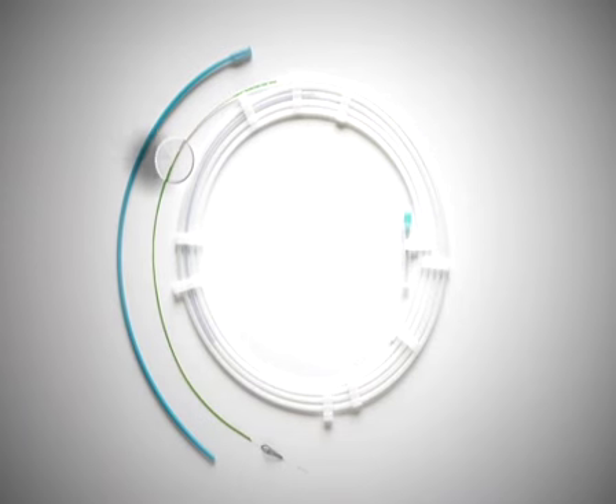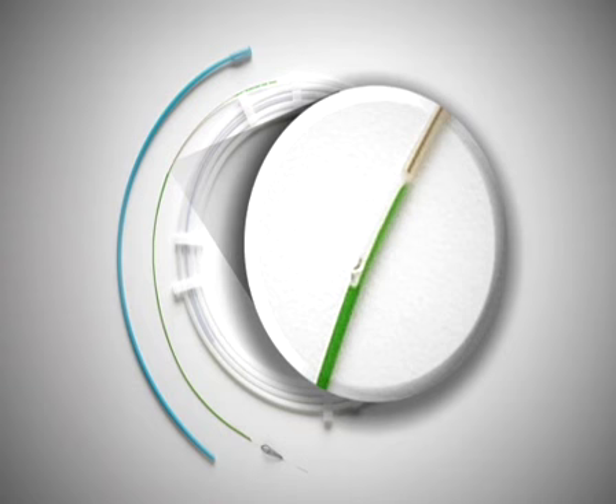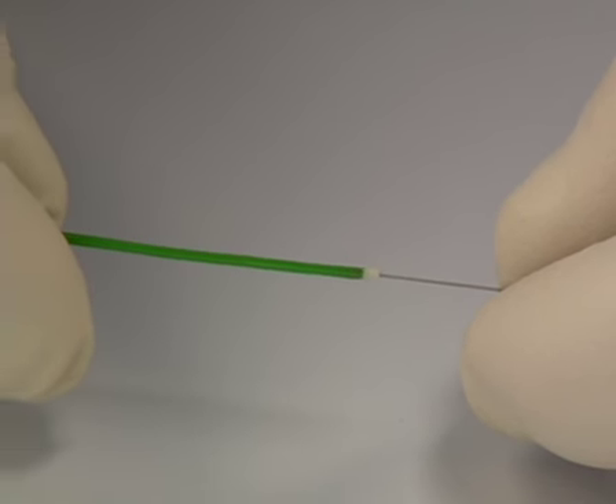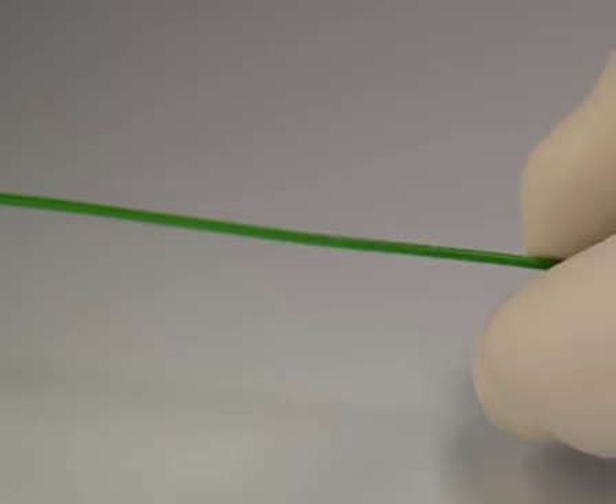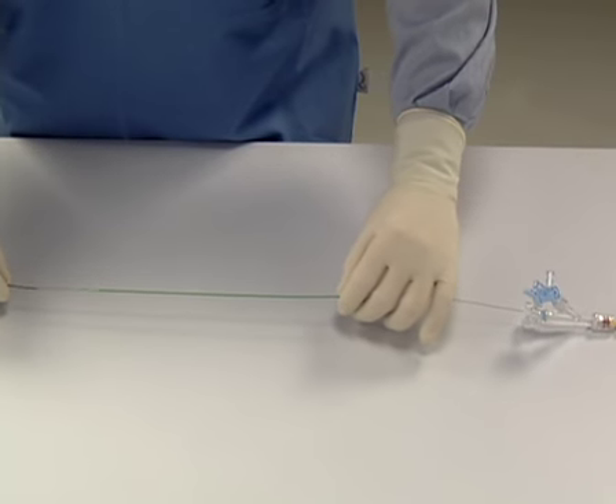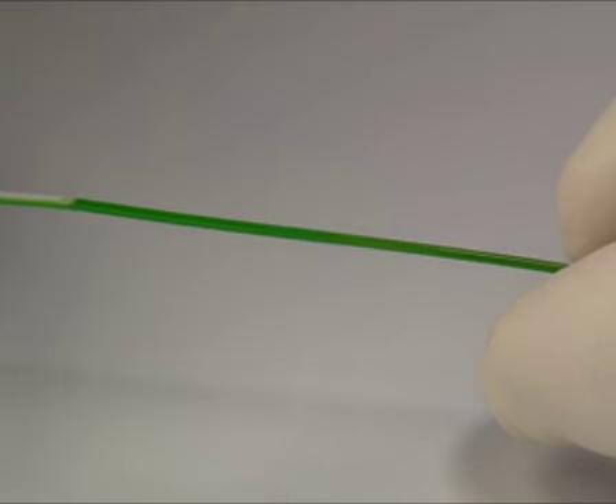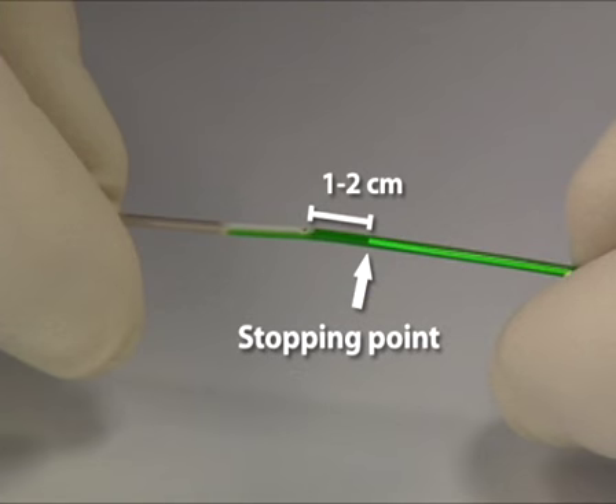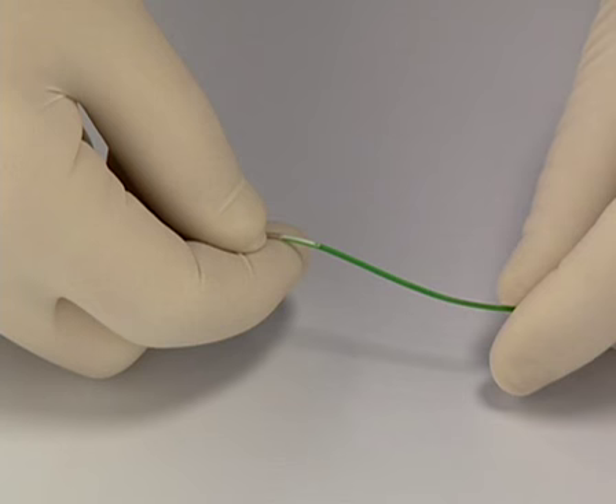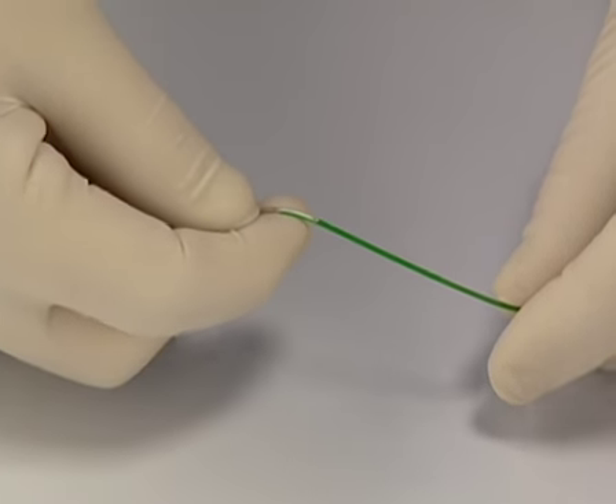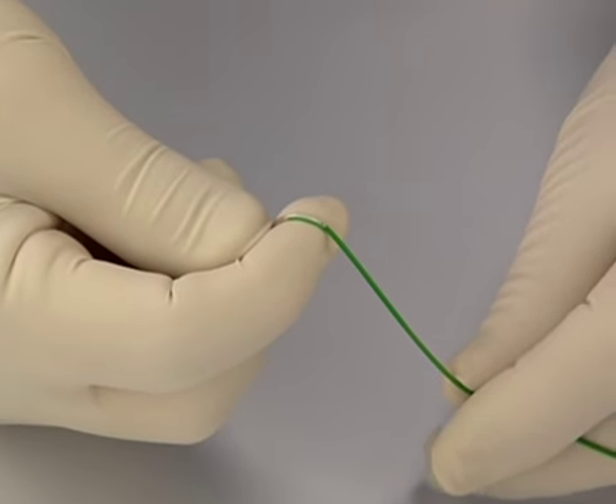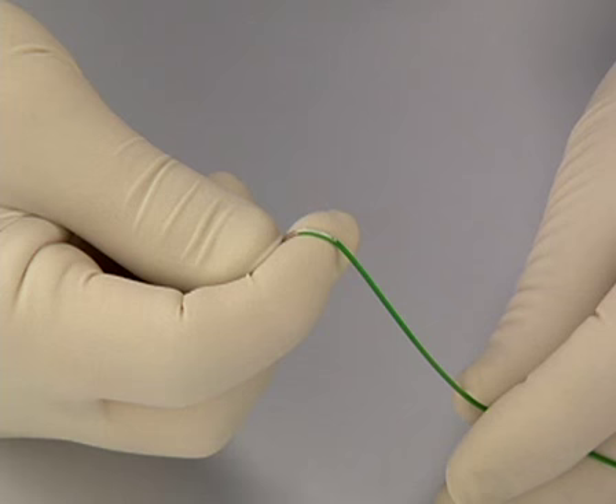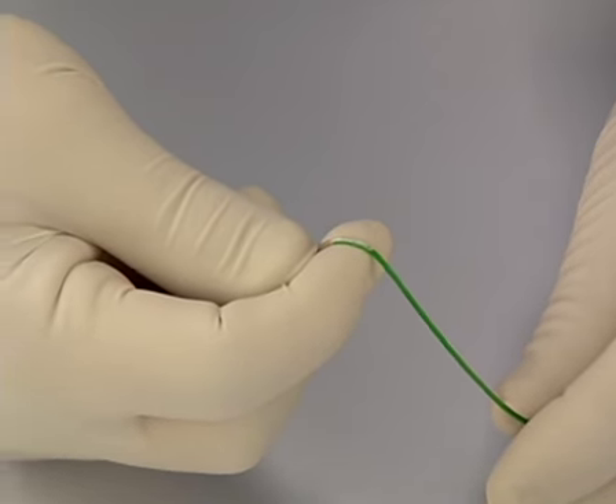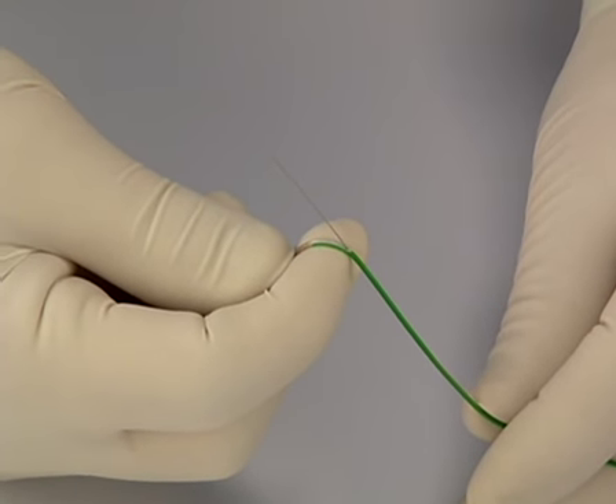First, locate the primary wire exit port by the white mark on the delivery end of the catheter. Load the delivery end of the catheter onto the primary wire and gently advance until the primary wire proximal end is 1 to 2 centimeters distal to the exit port. To aid in proper primary guide wire exit, form a gentle curve in the catheter over your finger, with the primary guide wire exit port at or near the apex of the curve. Advance the catheter to allow the wire to exit through the port.